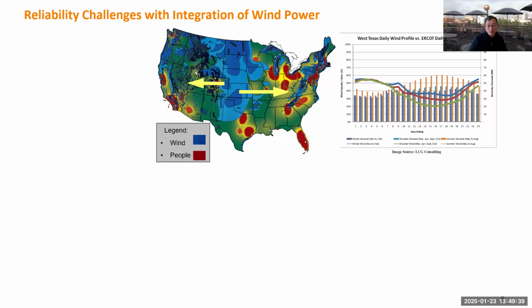So this example reminds us that when we talk about reliability, we cannot just use very simple math. We cannot just calculate that my system can generate this much energy and my system needs that much energy, so if the first number is bigger, I'm safe. No, that's wrong. You need to make sure that at any moment the power is balanced between generation and load. That's very important. Otherwise, in your network some violation will happen and some equipment will be tripped.